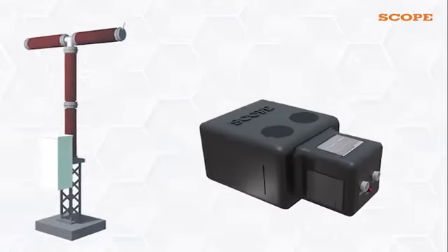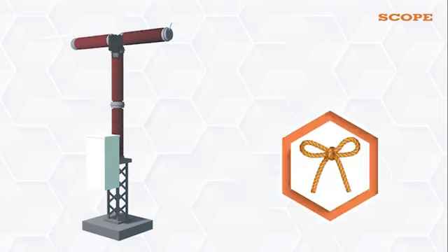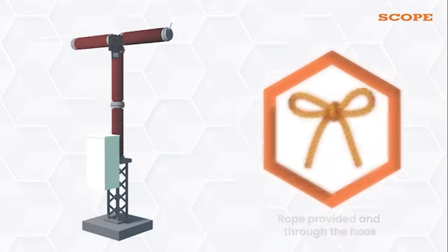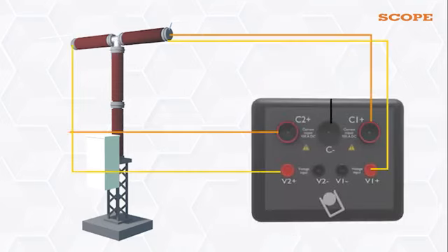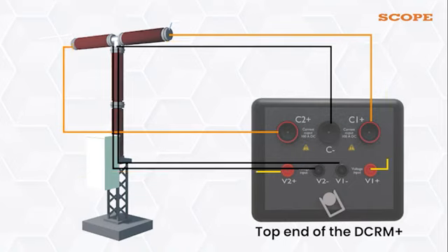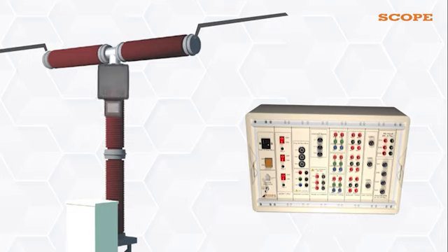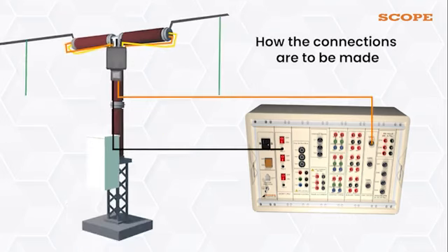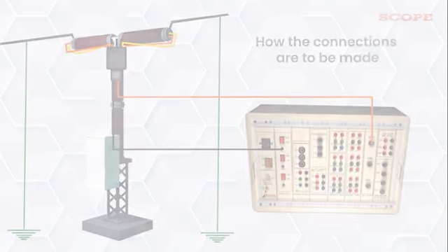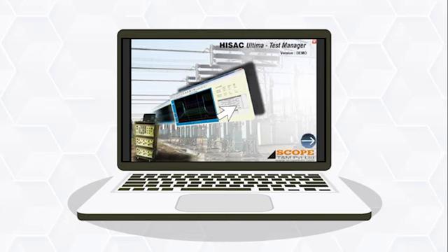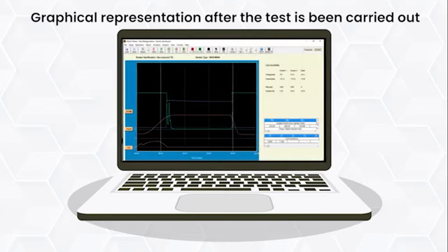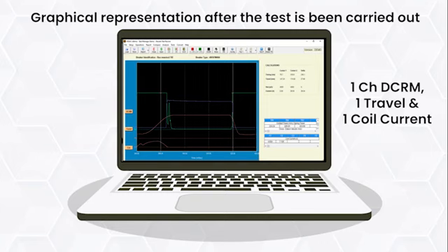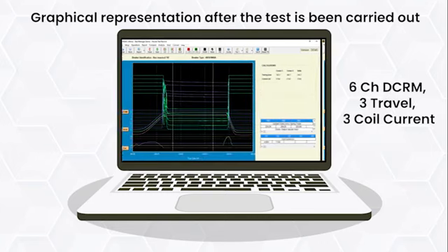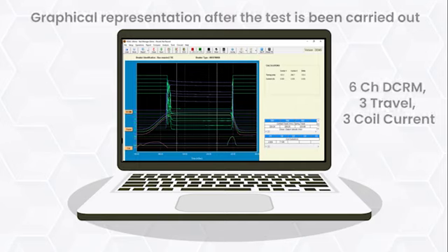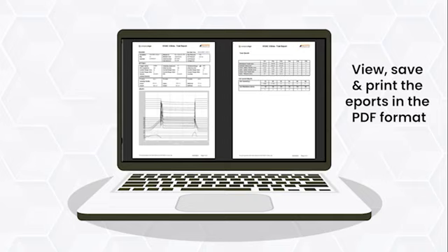Here, the DCRM+ unit should be hanged first properly and firmly through the rope provided and through the hook. After this, all connections to the breaker are to be made from the top end of the DCRM+. Here is the complete view of how the connections are to be made. After all the connections are made, PC or laptop software to take over. You can see the graphical representation after the test is carried out. We are showing you an example of the DCRM test conducted. 1 channel DCRM, 1 travel and 1 coil current. 6 channel DCRM, 3 travel, 3 coil current.